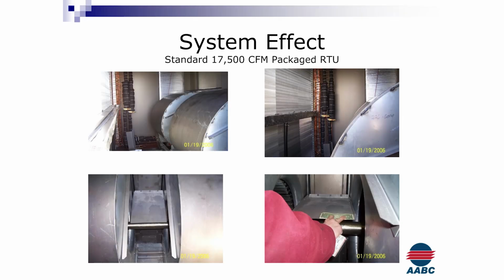The manufacturer was now baffled. What do we do next? The AABC contractor's a smart guy. He said, why don't we put in a vortex breaker? Just like if you had a pump. Sometimes you get some cavitation or something going on with the pump, and you want to put a vortex breaker in. We just put in this little piece of metal. Broke up the vortex. Guess what happened?